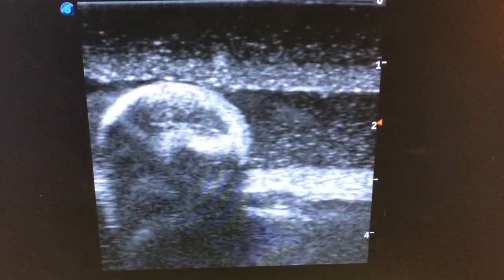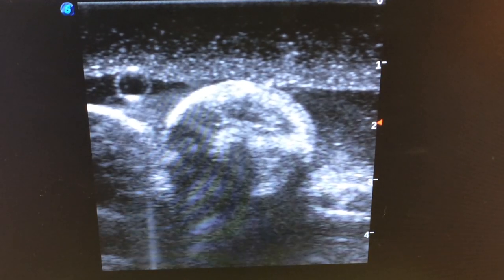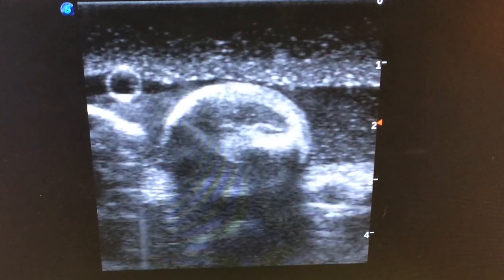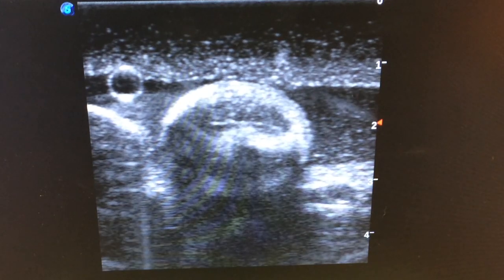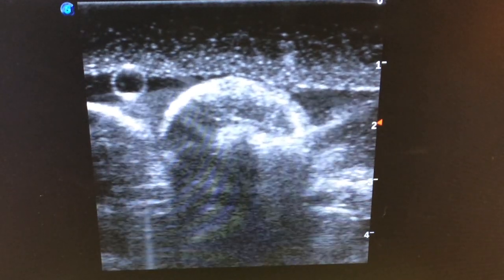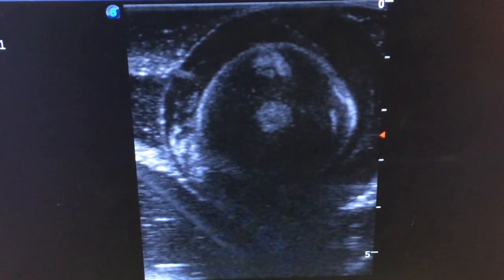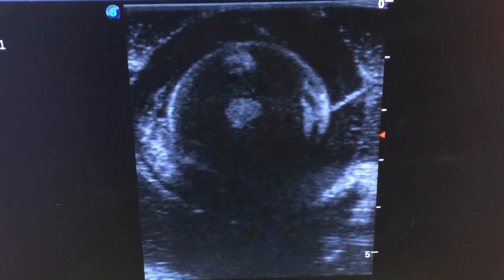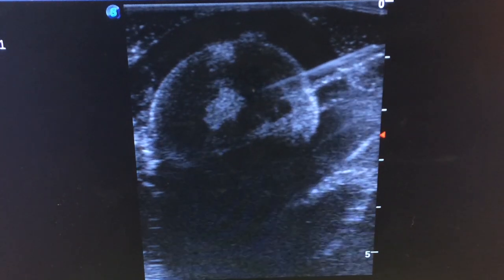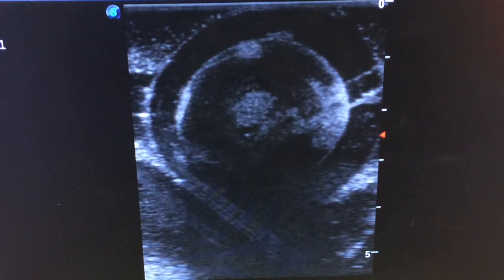Here is a grape that we're going to try to get a true cut biopsy on. You will see the shape of the needle as it comes into the ultrasound beam is different, because it will actually have that little divot for the tissue sample. So you can see the point and then the rectangular shape behind it, which is where the sample is taken from. Here is an egg yolk to do the same thing — you're not collecting a sample at the point, you're collecting your sample from behind the point. And once again, you can see where you've been.